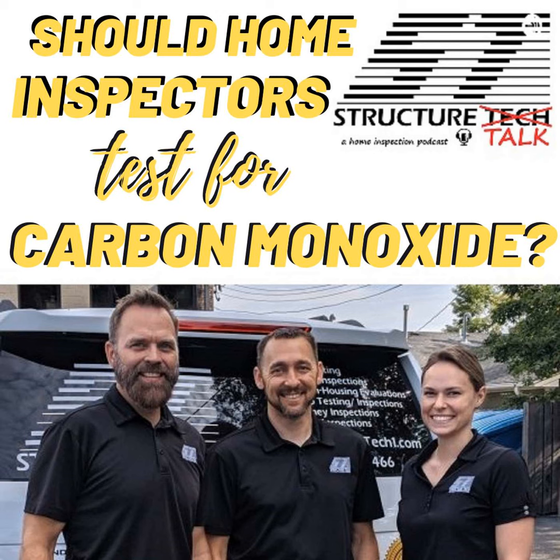But I've personally been involved in probably a half dozen transactions where I found high levels of carbon monoxide at a furnace. I called it out. Then later on, the contractor says, no, it's fine. And then we figure out, wait, whose was last calibrated? And ours was, and they're wrong about it. And they end up sending somebody else, and they say, oh yeah, our equipment was off.